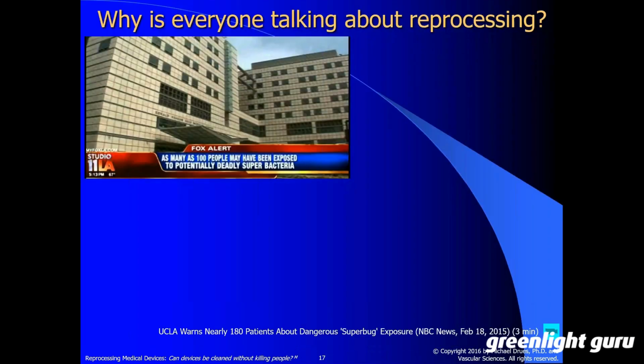So how does this relate to validation, and how is this a validation failure? It's very simple. If your device is designed to be reused and reprocessed, then it's just as important to validate your reprocessing procedure as it is to validate any other aspect of your device: your usability, your mechanical properties, your biocompatibility, and so on. It's just as important. And to me, this is common sense. This is basic biomedical engineering.